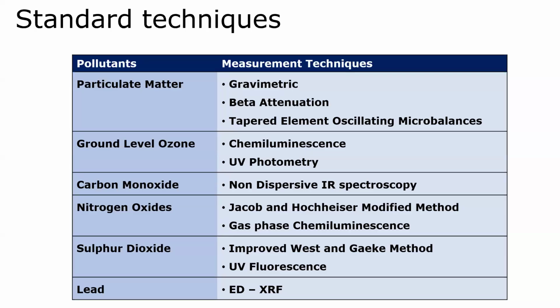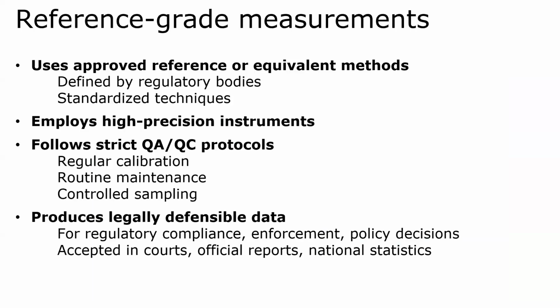Lead is a very toxic pollutant. For lead, we generally use EDXRF, X-ray. X-rays will be used to knock out some of the inner shell electrons, and from outer shells, some transition will happen, through which again some X-rays will be emitted, which we call characteristic X-rays. By measuring the characteristic X-ray intensity, we can quantify lead. Okay, these are the standard techniques we use for measuring all these air pollutants.